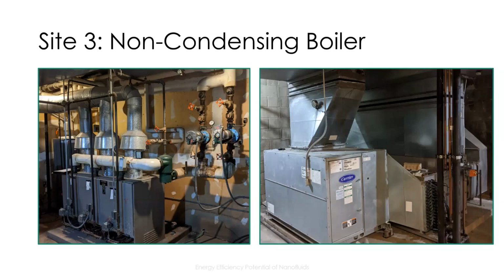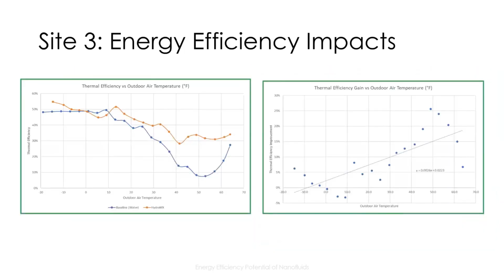Our data analysis involved a linear regression of the gain in efficiency based on outdoor air temperature as a proxy for weather data. And then this regression was applied to the baseline weather data to get a gain. The left-hand graph here shows a higher efficiency in most cases in the nanofluid period, with the orange line being higher than the blue line. It also shows that the boilers peak at about 50% efficiency, which is much lower than would be expected.